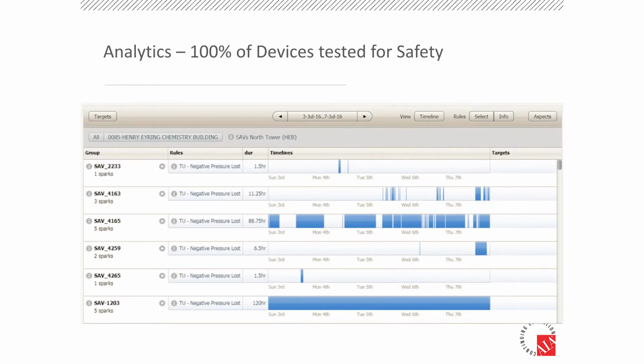So that's a time series view, and then you say, well, that's just one lab. Is this happening in other laboratories in the building? And that's where we can use the analytics tool, the analytics piece of the monitoring platform, and that looks like this. So what we're actually looking at is negative pressure lost. In other words, when there's an indicator here in color, that's saying negative pressure in this laboratory was lost, so it's an unsafe space for students. The platform is looking at all 94 laboratories, and it's only presented the issue in 6. We can see the time frame over which this negative pressure issue is prevalent in each of these labs. So we can take this information to the laboratory controls guy or the facility staff, and they can fix it.